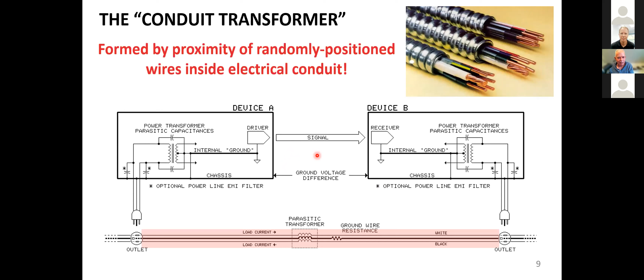So there's the transformer that's in the conduit. This magnetic induction is strongly affected by geometry. It's highest with randomly positioned wires in conduit, which unfortunately is how buildings are done. It's much lower with uniform geometry holding the position.